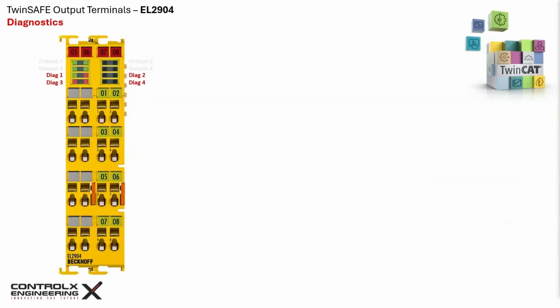Diagnostic 3 and 4 red LEDs indicate internal terminal errors. These errors lead to shutdown of the terminal and it must be checked by Beckhoff or replaced. As I mentioned for the EL1904, do not modify any COE parameters on the EL2904 as well. Any modification is seen by TwinSAFE as device tampering and immediately locks itself into a permanent fail-stop state.